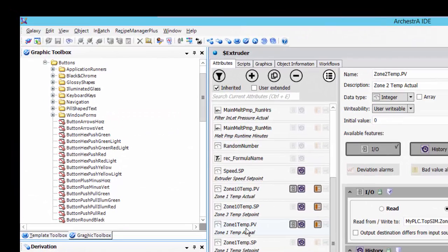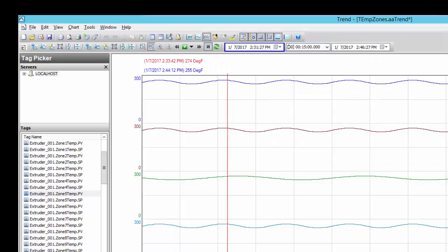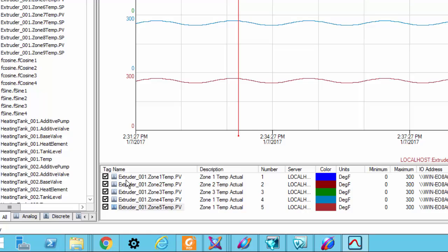Let's have a look at what we've set up so far. We're here in the IDE, and we have a template called Extruder with some attributes — Zone 1 temperature, Zone 2 temperature, Zone 3, and so forth. All of these are being stored in the Wonderware Historian with history enabled. In our trend application, the first instance of the extruder template is called Extruder_001, and we can see the five zone temperatures trended over whatever time period we'd like. But this trend may not tell the whole story the operator needs — perhaps they just need to know the averages of these temperatures over time.